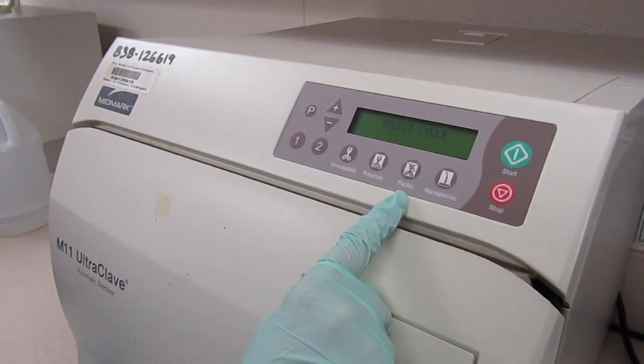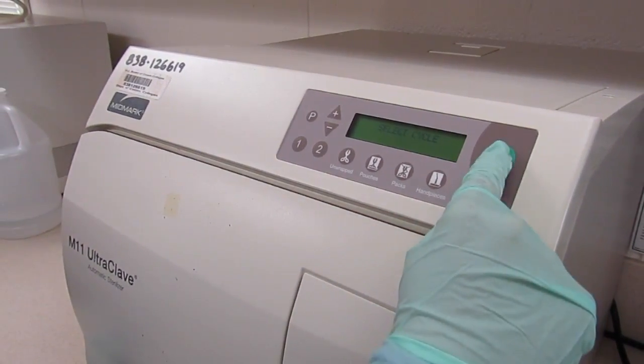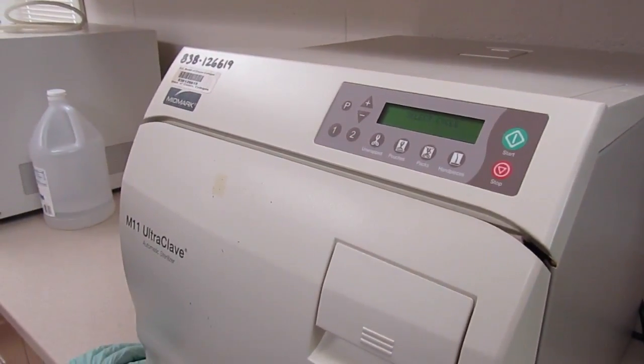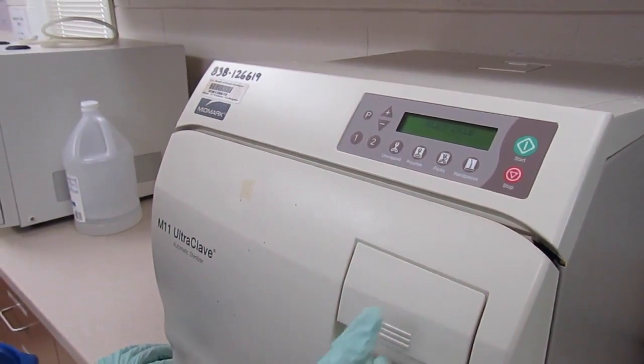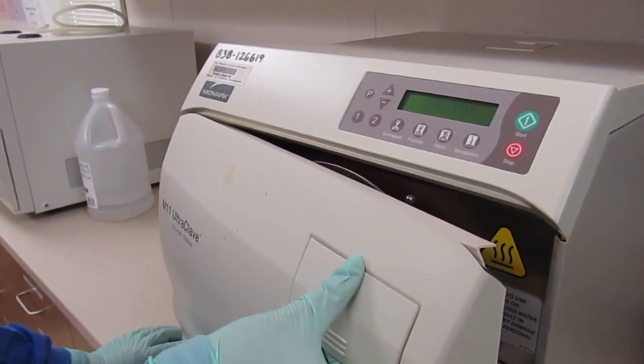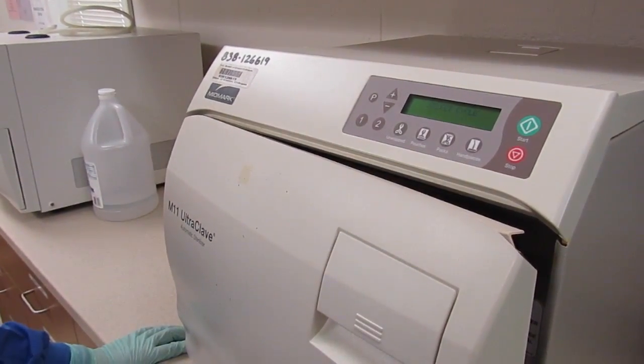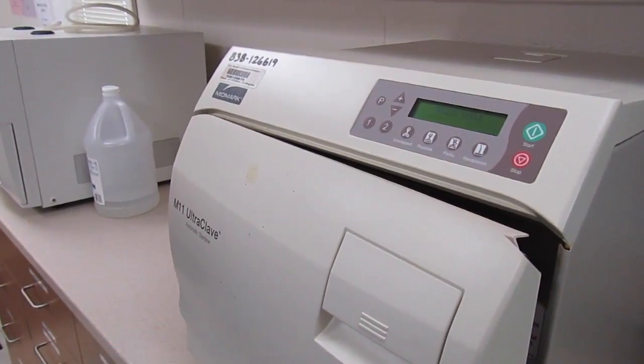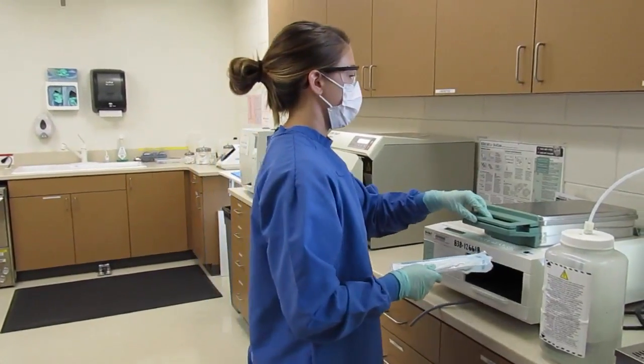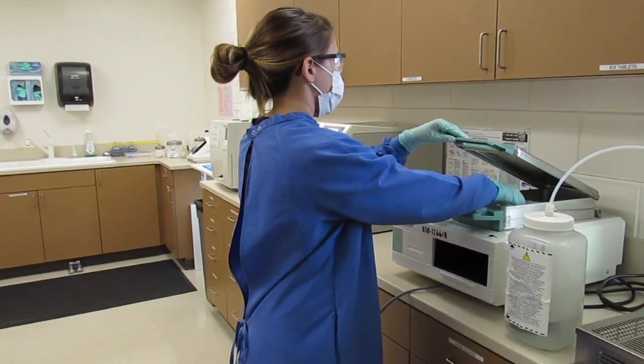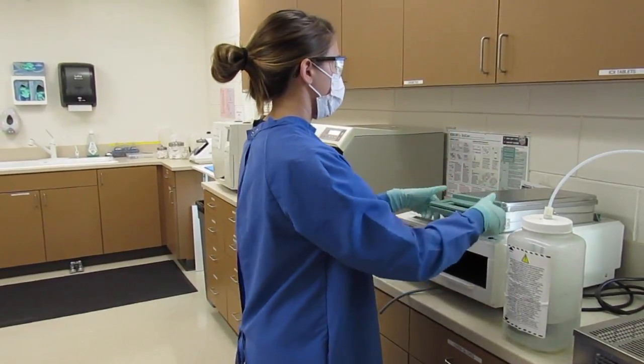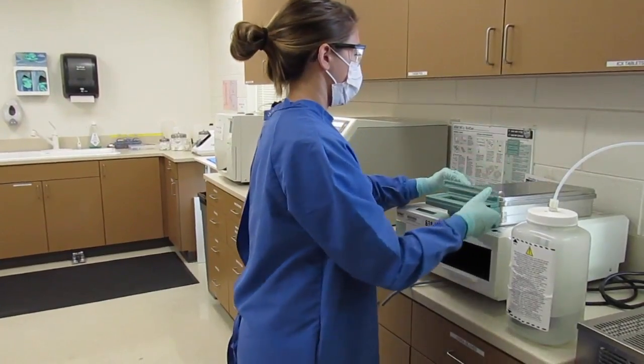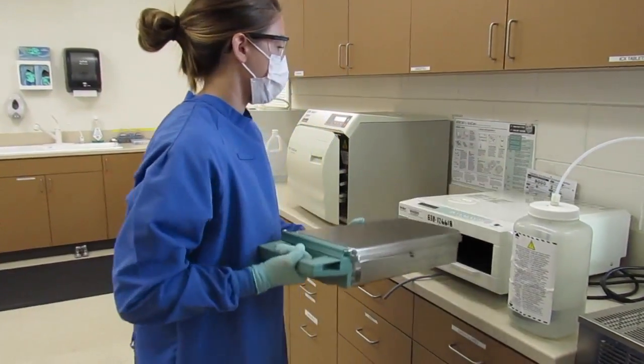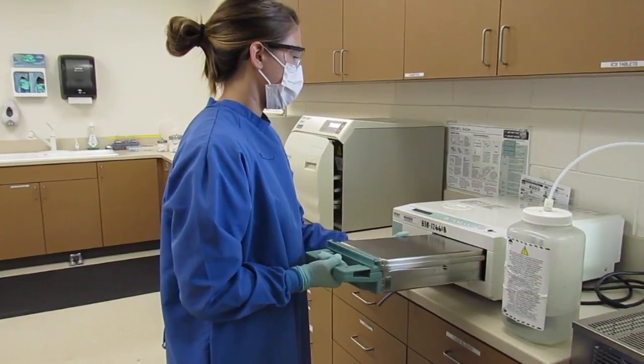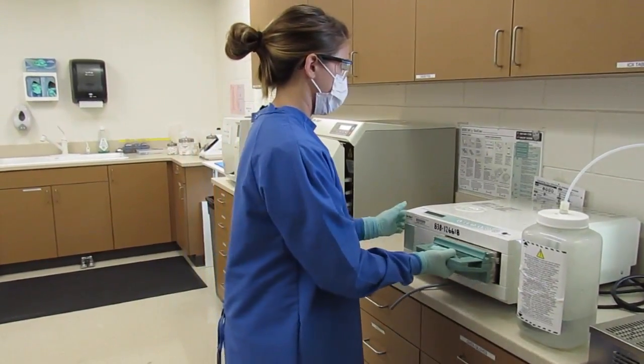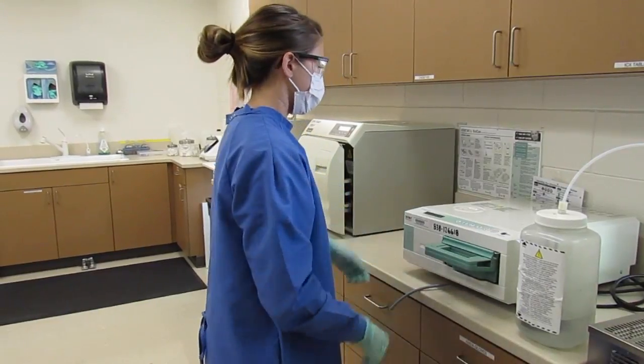Once the cycle is complete, the dry and ready lights are flashing and the unit beeps 5 times. At this point, you will leave the door cracked until the drying cycle ends, and then the ready light is flashing in the unit and it will also beep 5 times. Tanya will be loading her wrap and packaged instruments into the Statim. She will then close the lid until she hears a slight snap and then move the carry handle to a closed position. She will then put it inside the machine until it clicks.